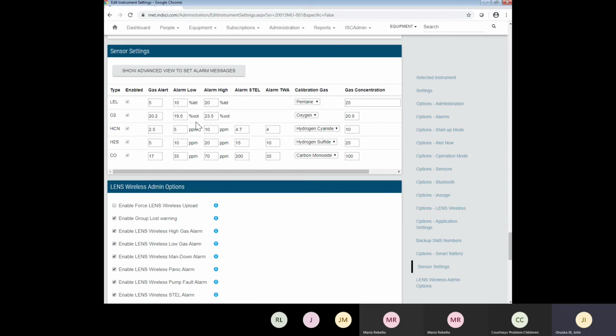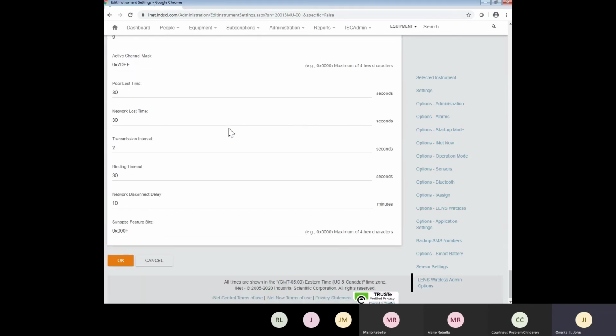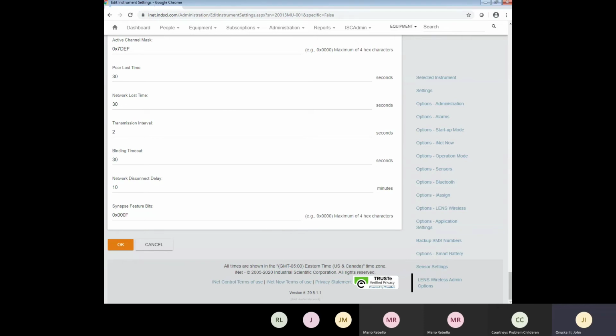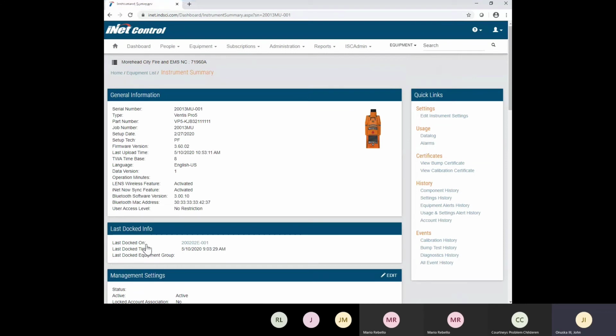So say if you have a particular low alarm that you want to use or high alarm, you would do that. Once you've made the changes that you want, you come all the way down to the bottom. You would just say, okay. I'm going to click cancel because I don't want to accidentally make any changes to your instruments. And then what you would do is you would take the instrument, stick it onto the docking station, and the docking station will actually push all those changes for you.